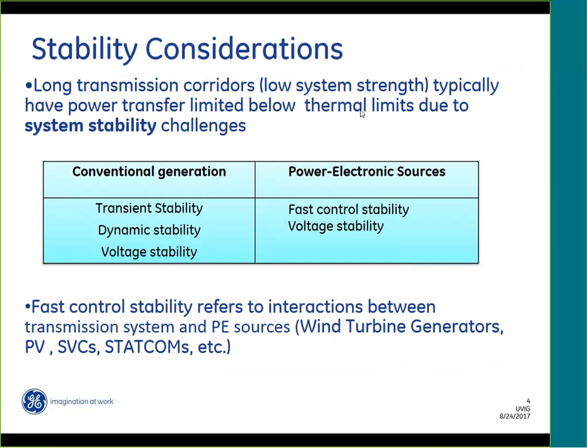your conductors in that line or that transmission corridor, you will find some other type of limitations that are typically stability limitations. So if we think about more conventional systems with synchronous generation, those stability limitations are associated with transient stability. Transient stability has to do with the machines losing synchronism to each other on both ends of the transmission corridor. Dynamic stability is related to electromechanical oscillations through the corridor. So that will be power oscillations through the corridor, or voltage stability. So these are the problems that the industry is accustomed to see in relation to conventional generation.